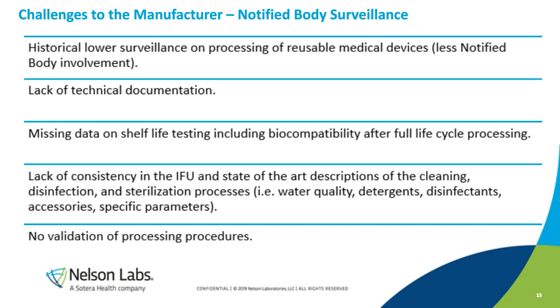There is also historically a lack of technical documentation because it has not been necessary to include these devices in the medical device directive previously. Associated with this, there may be missing data on shelf life testing, including biocompatibility after full cycle processing. There is a definite lack of consistency in the IFU and descriptions of the cleaning, disinfection, and sterilization processes. This also includes aspects of the processing like water quality, detergents, disinfectants used, all the accessories that need to be used for these processes, and the specific parameters that need to be followed. Sometimes there is actually no validation of these processing parameters, so we just have instructions and IFUs that have not actually been validated.